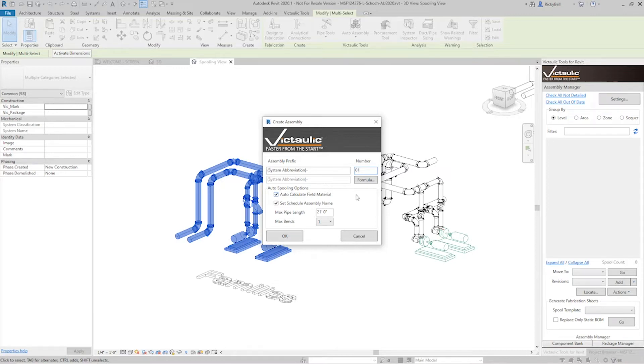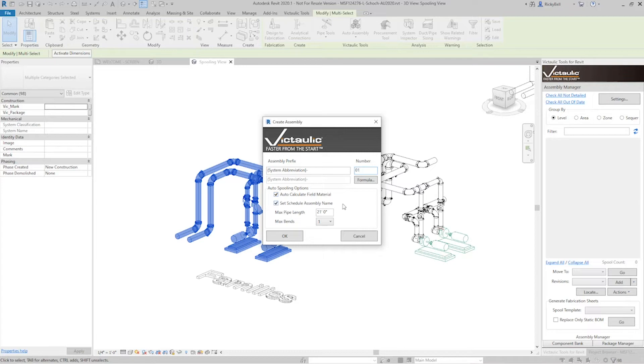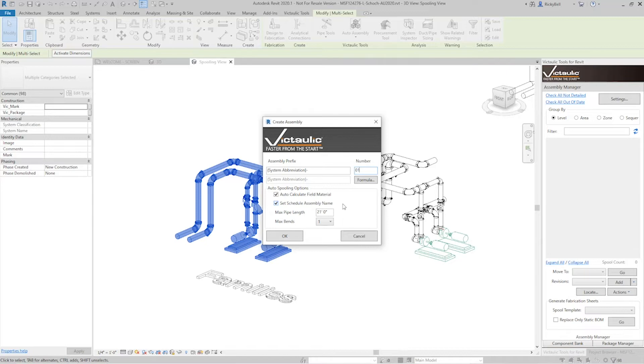So let's take a look at the auto spooling options at the bottom. Auto calculating field material is important. These are the joints that are going to be between your spools. They should be marked as field material. Set schedule assembly name. This is crucial with making sure that your spools don't become typicals. Revit likes to group like assemblies together. And as you're going from system to system, that could be not what you're looking for at all.